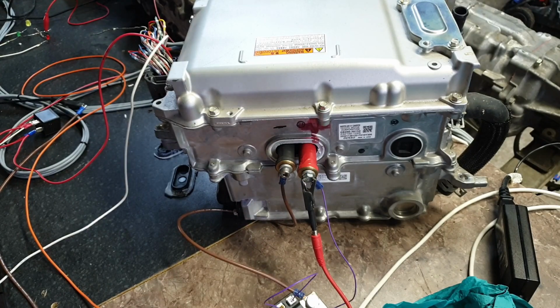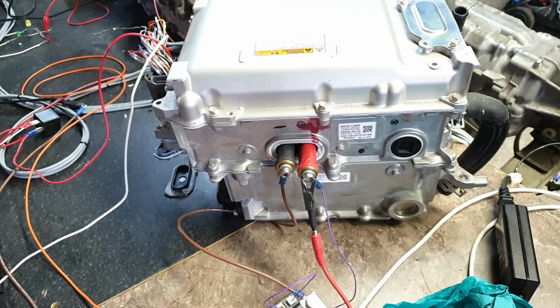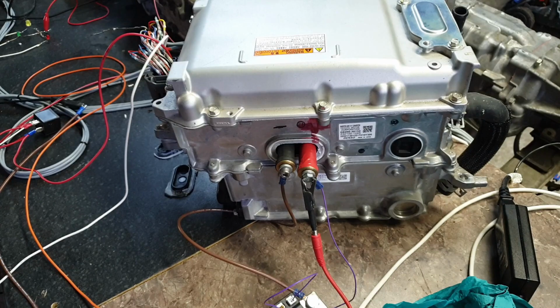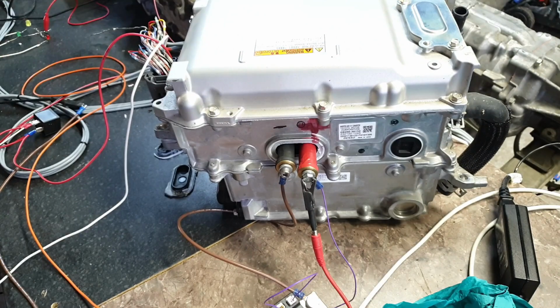The reason for that is if we don't do that, if we choose to use the existing points, we'll be limited by the current carrying capability of the boost inductor in the inverter. And if we exceed the rating of that boost converter inductor for long enough, the inverter will go boom. Not good. So this is where we connect our high voltage.